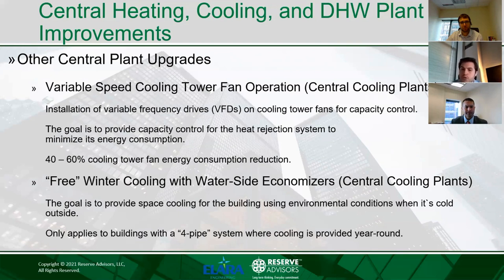Please note that not all buildings have a four-pipe system. A two-pipe system is a more common application for high-rise condominium buildings. But if your building has a four-pipe distribution system and requires air conditioning during winter time as well, what we suggest is installing a water-side economizer, and that can provide free cooling for the building using environmental conditions when it is cool outside. So instead of using electrical energy to provide air conditioning, it would utilize the environmental conditions, the cold air outside, to provide air conditioning for the spaces.